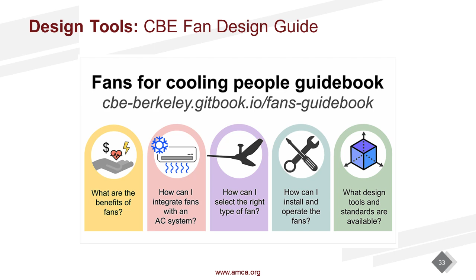The design tool actually uses a lot of the information and guidance in that document to parameterize fan design for a space. You can tell it the area of concern, the dimensions of that space, and a target airspeed that you found using the CBE thermal comfort tool to meet a certain set of conditions. You can use tools like this to optimize that design with real fan performance data.